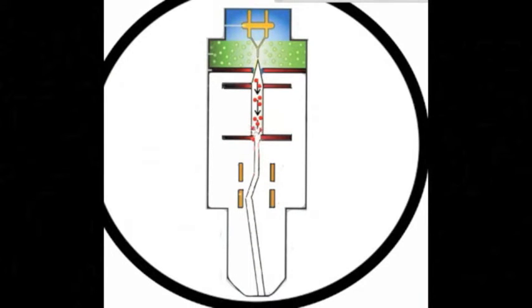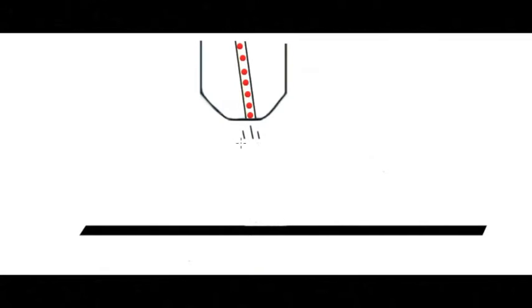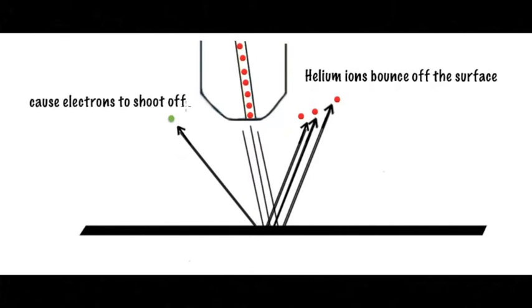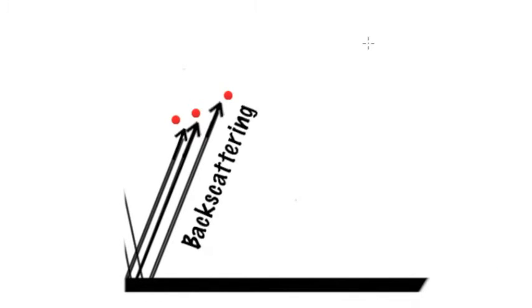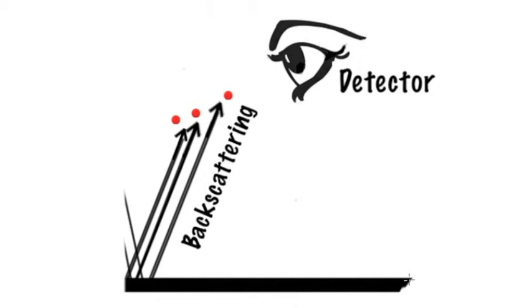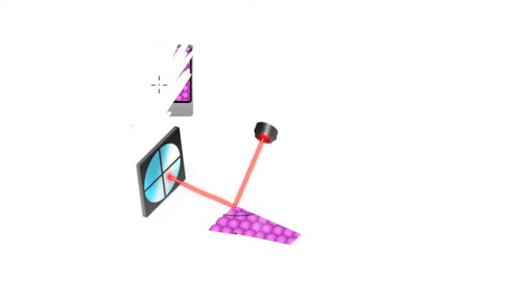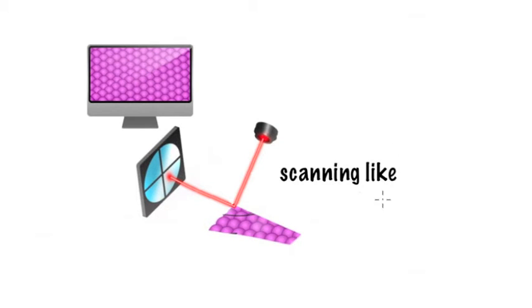To generalize it, helium molecules are funneled to the apex of a needle that is only 3 atoms wide. This apex is under a large positive potential that strips helium atoms of electrons as they pass through. This tip can then shoot these helium ions out where they can be guided by electrostatic lenses to the sample surface. These ions then contact the surface and either bounce off or cause electrons to shoot out of the material. The ones that will bounce off the surface of the material are called backscattering ions and can be detected by the many detectors. Based on the angle and other factors, the computer can begin to get a rough idea of the surface at that point. This helium ion can also cause secondary electrons to be ejected, which can be used for further detail. Now imagine this happening with hundreds or thousands of helium ions as the tip rasters across the surface like a printer. Using this, the computer can generate a 3D image of the surface of the material.